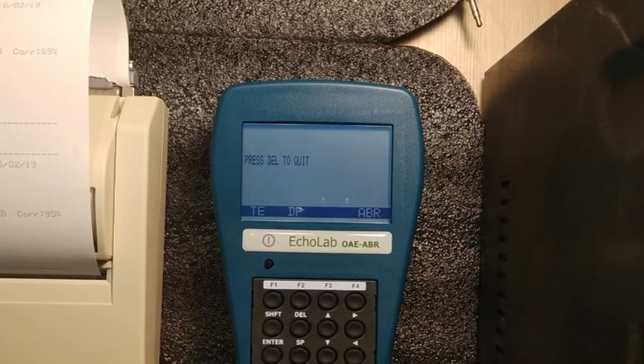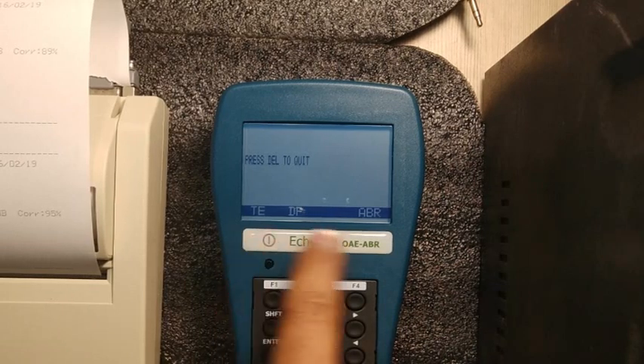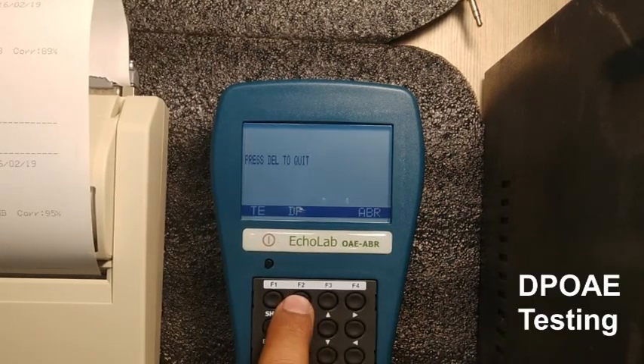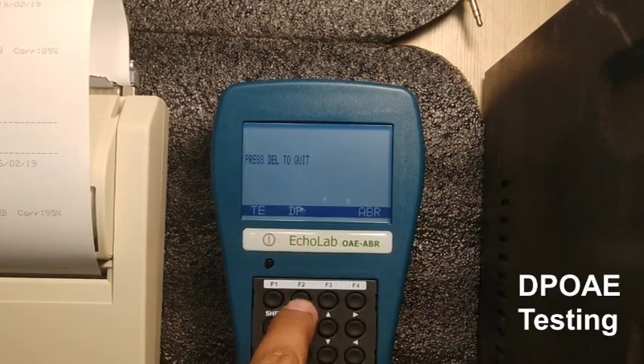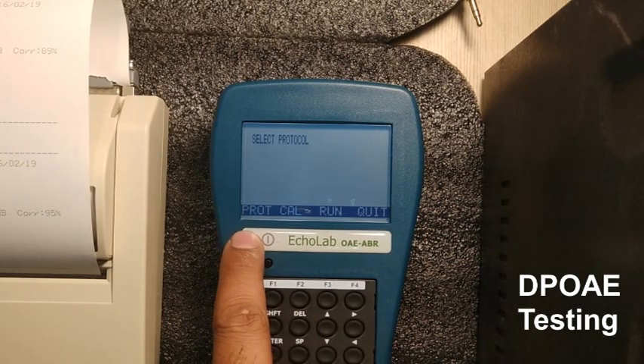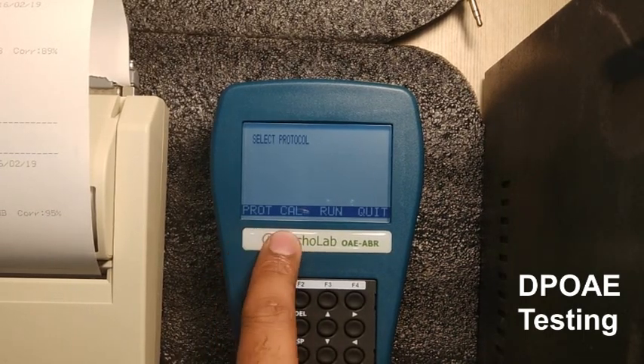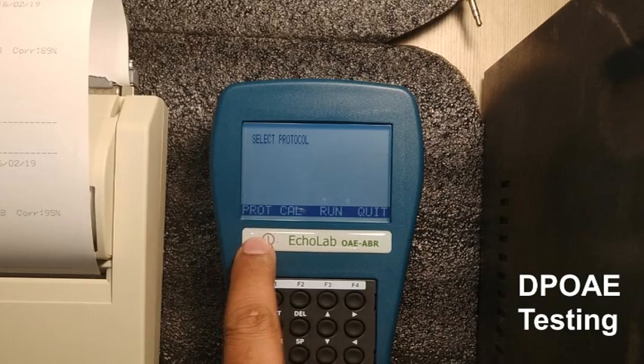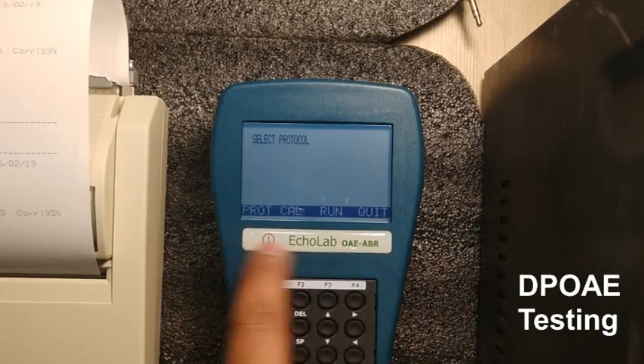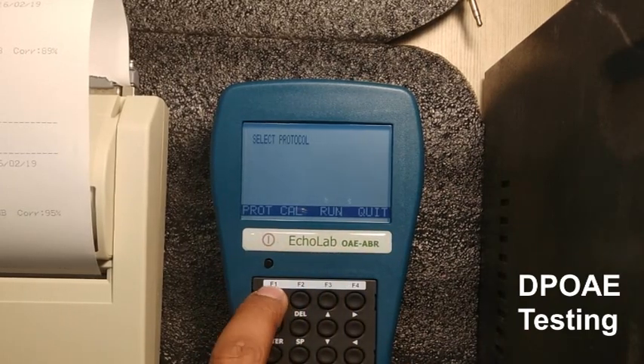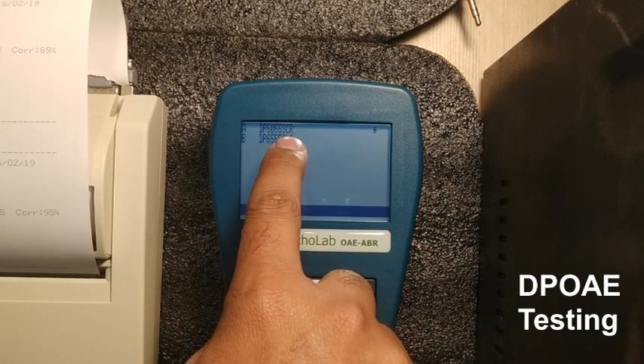Now we will do the DPOAE test. So now in the test menu we will press F2 to go in the DP menu. I'm pressing F2. You can see the same options that we saw in TEOAE: protocol, calibration and run. So first of all for executing the test we will select the protocol. So I'm pressing F1. We are in the protocol menu where you can see two options, screener and clinical.